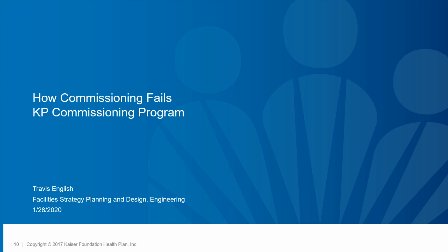And this is the emphasis of our commissioning program. We want our commissioning teams to get the building systems to work. And I hate to sound like a total skeptic or a total naysayer, but if you designed it or if you intended it, but you didn't measure it, then in my book, it didn't happen. We've just seen this way too often. We can only know that those building systems work when we have the data to prove that the building systems work according to their design intent.